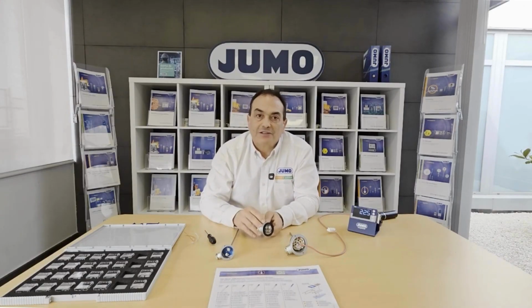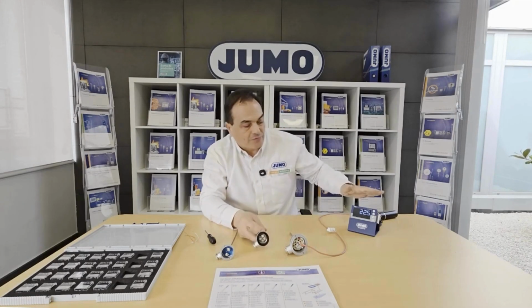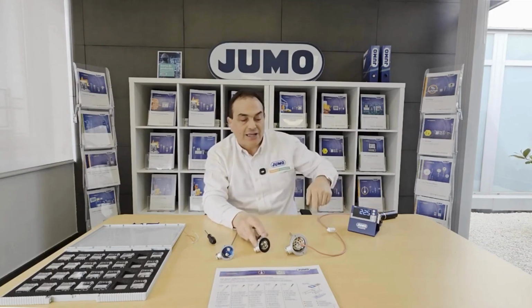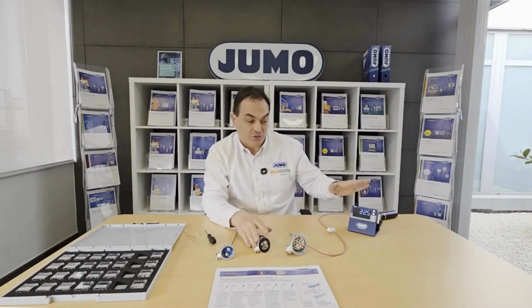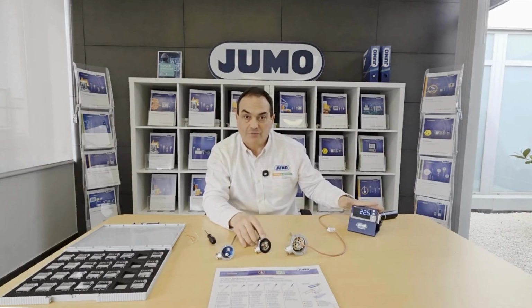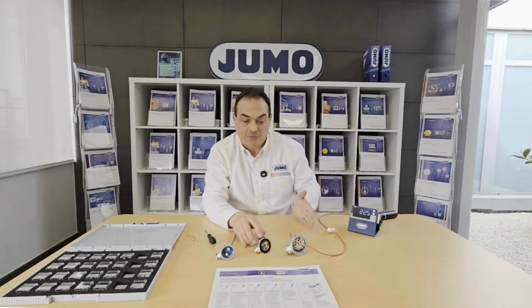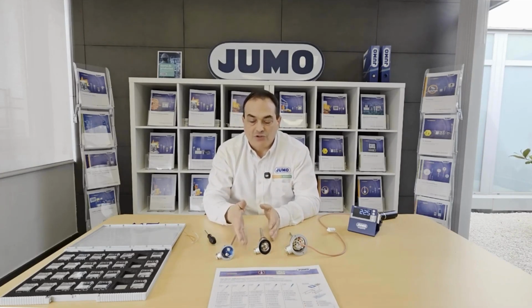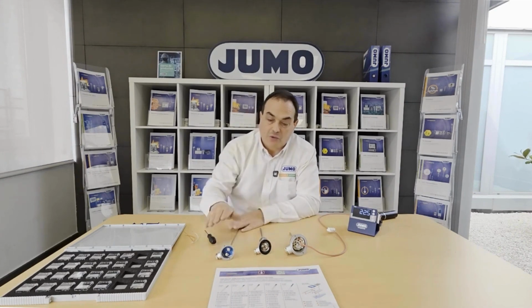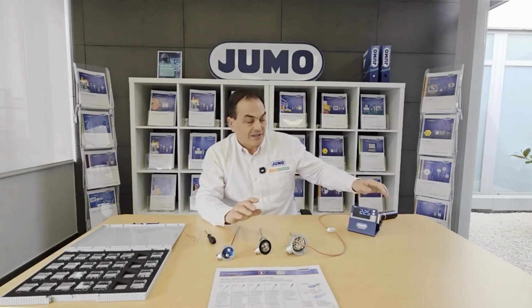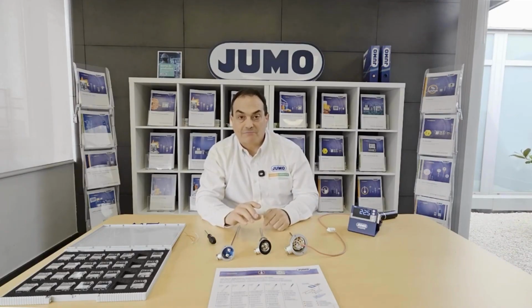The reason for connecting them in these 3 ways is to try to reduce the error that the length of cable between the sensor and the electronic device adds to the system. However, it's still another resistance you have to take into account. That's why we associate a 2-wire sensor with being less accurate than a 3-wire or a 4-wire one, because what the electronic device does is automatically subtract that resistance.